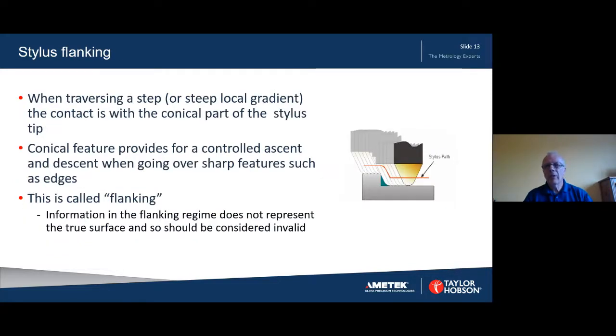Another important consideration is stylus flanking. This is where the contact is between the surface and the conical part of the tip. In the area shown on this graphic as green, no useful information is gathered from the surface. In fact, if this were a truly sharp step as shown, the system would be measuring the side of the tip rather than measuring the surface. Stylus flanking should be avoided. Where flanking does occur at the end of the measurements, the areas affected can usually be discarded.